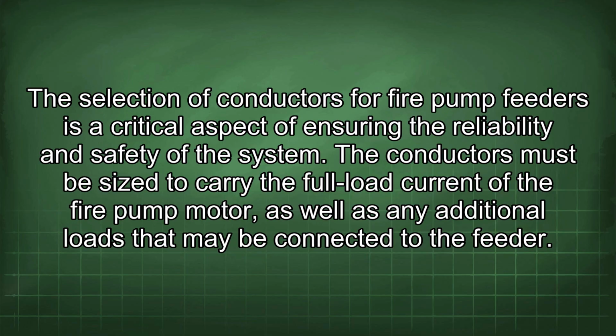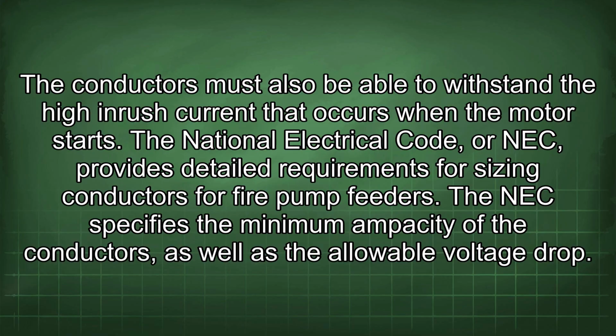The selection of conductors for fire pump feeders is a critical aspect of ensuring the reliability and safety of the system. The conductors must be sized to carry the full load current of the fire pump motor, as well as any additional loads that may be connected to the feeder. The conductors must also be able to withstand the high inrush current that occurs when the motor starts. The National Electrical Code, or NEC, provides detailed requirements for sizing conductors for fire pump feeders.